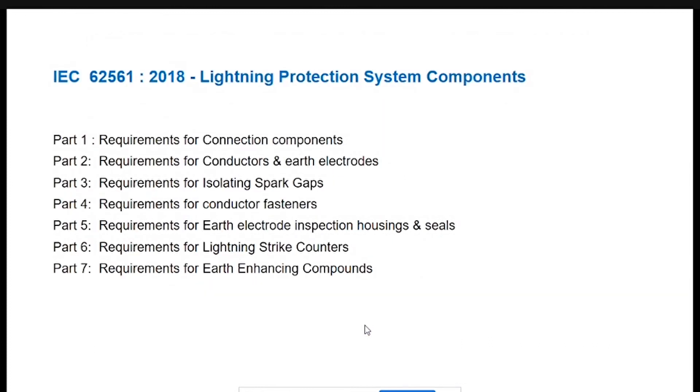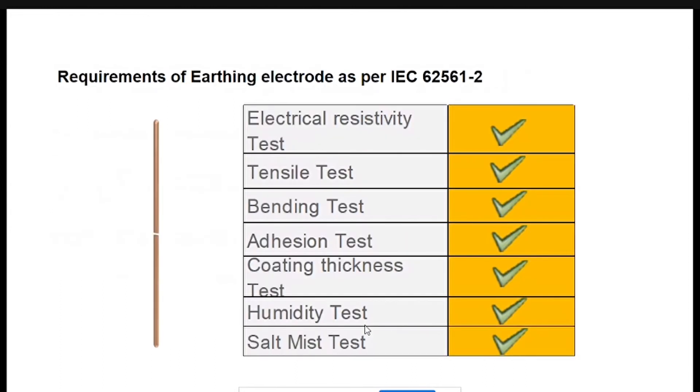When you use the earthing electrode, there are minimum dimensions and configurations recommended. It has to adhere to the requirement of IEC 62561 Part 2 for the earth electrode and IEC 62561 Part 7 for earth enhancement compound.